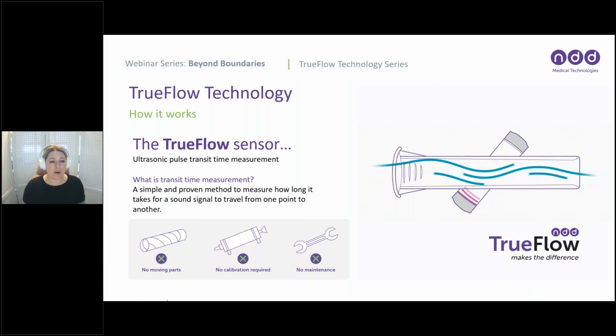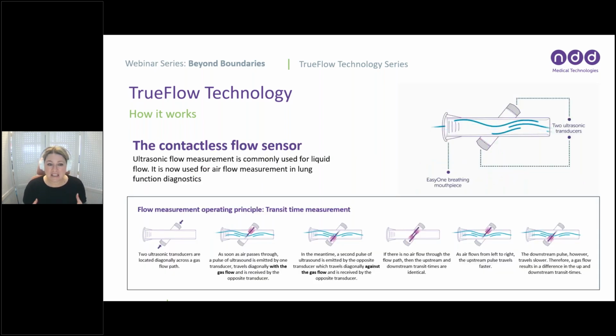All right, so how does it work? The TrueFlow sensor uses an ultrasonic pulse transit time measurement, or that point-to-point ultrasound. So this is a simple and proven method to measure how long it takes for a sound signal to travel from one point to another. Using this technology, there's no moving parts, there's no manual calibration required, and there's no maintenance. So the contactless flow sensor is commonly used for liquid measurement or for liquid flow, but we have used it for airflow measurements in lung function diagnostics.